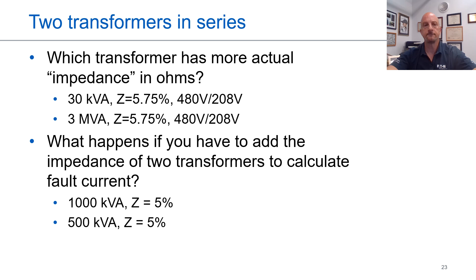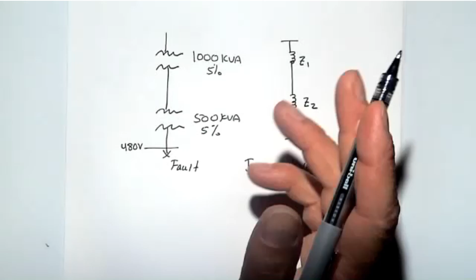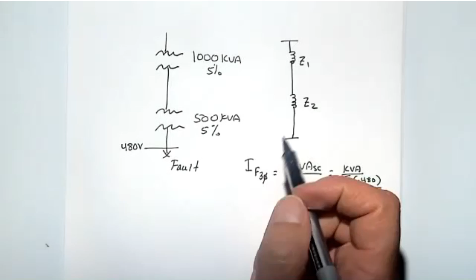What happens if you have two transformers in series? How do you add them together? Let me show you that as a quick calculation. Now, here's a situation that you also have to understand. What if I have two transformers in series and the ratio of those transformer kVAs is not 10 to 1 as we've been assuming? Then we can't just say it's an infinite bus above the downstream transformer. In this case, these two transformers are relatively similar in size. We want to add them in series to create that series impedance so that we can figure out our total fault current at this point on the system.